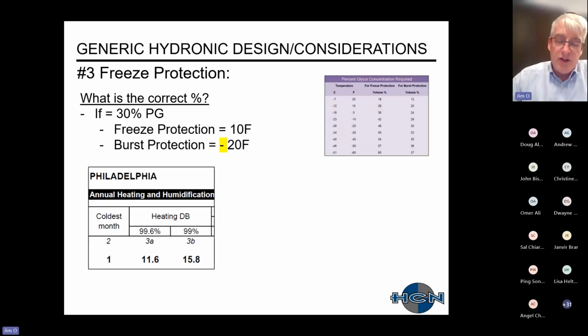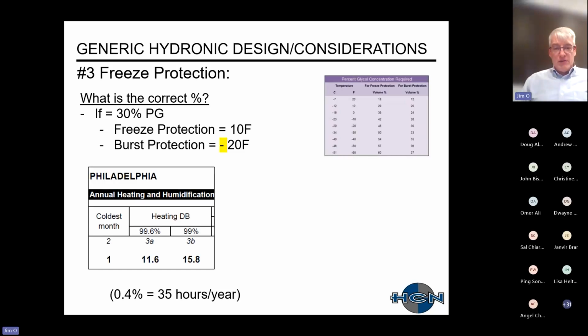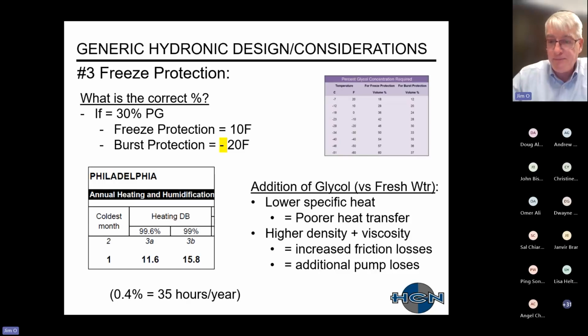I'm in Philadelphia. So here is from ASHRAE, your annual heating design dry bulb temperature. This shows that for 35 hours per year, the temperature could get to 11 degrees. Once again, in my experience, about every 3 years or so we'll get a cold snap where it gets down to 11 or 0 degrees for a couple of days.